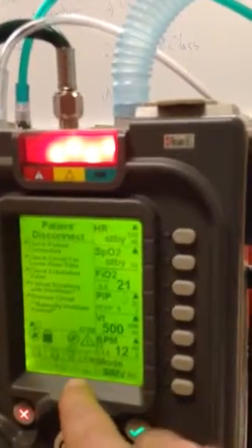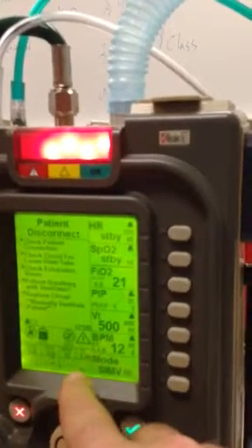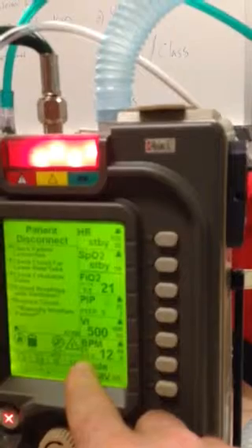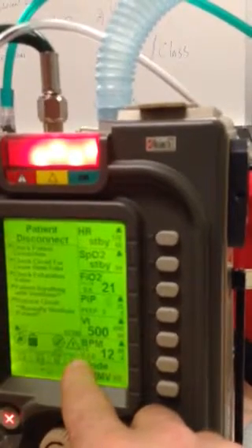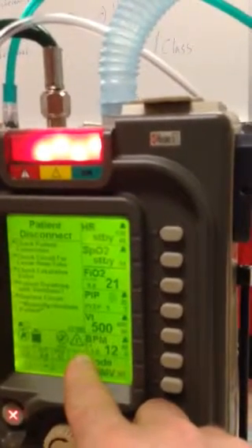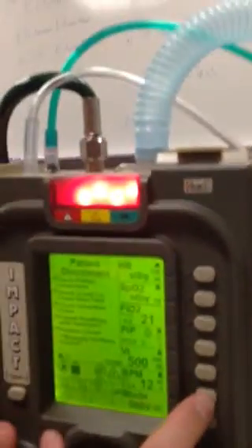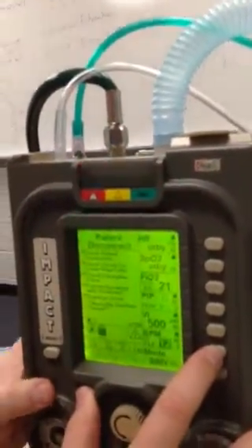Okay, so you mentioned to me this morning that an I time of perhaps 0.8 is good, and I was noticing during that time that if you lower your I time, it allows the patient a longer time to exhale. Correct. So basically this number that I'm pointing at is like a 1 second inhalation and a 4 second exhalation. Is that correct? Correct.